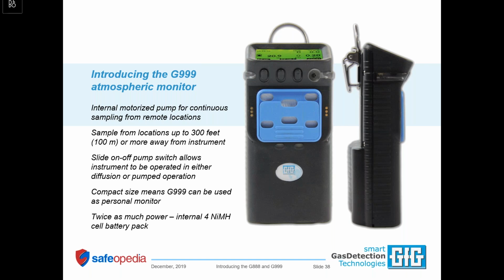The 999's big difference is that you have the available option of an internal pump. Most of the time, we'll probably be shipping the unit out with an installed internal pump. Why wouldn't we want every instrument to have one? Well, if you don't need a pump, another benefit of the G999 is that we have twice the power supply that we have in the 888 or in a G450 or G460.